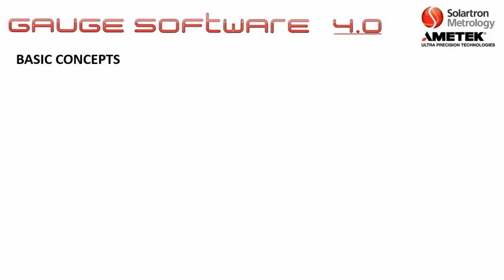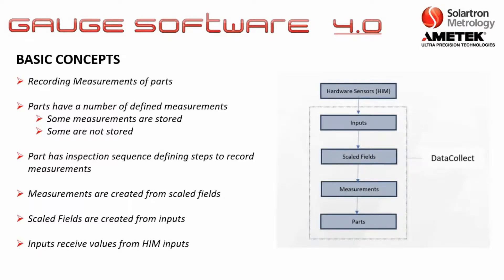Before going into the basic training, let's go through some basic concepts. Gauge Software 4.0 is fundamentally about recording the measurements of parts. Parts have a number of defined measurements — some are stored and some are not. The part has an inspection sequence defining the steps to record those measurements. Those measurements are created from scaled fields, the scaled fields are created from inputs, and the inputs receive values from the hardware interface module. Here is your basic diagram illustrating this.